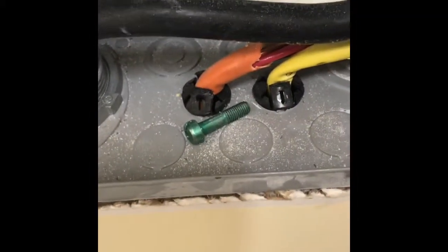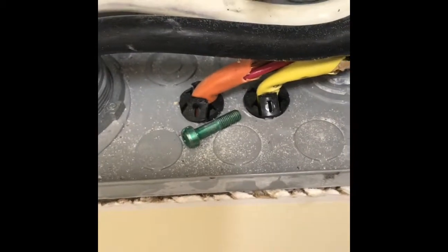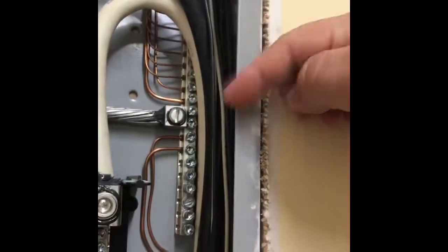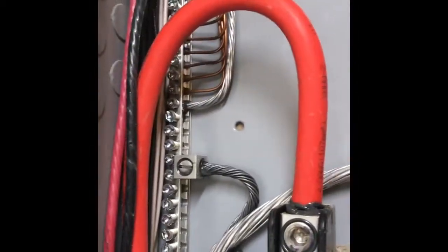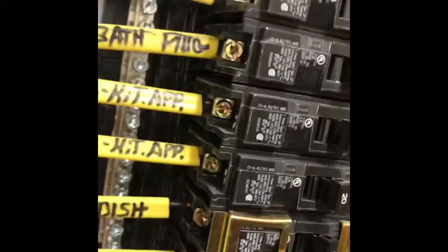Great electricians, what they'll do is they'll leave that screw right there. That's called the bonding screw. They'll leave that screw detached and leave it in the bottom, showing that the ground system is grounding out the box, is grounding out the system, and it's running out to the main panel, but it's not ever bonded to the white. That's going to be all your neutrals.